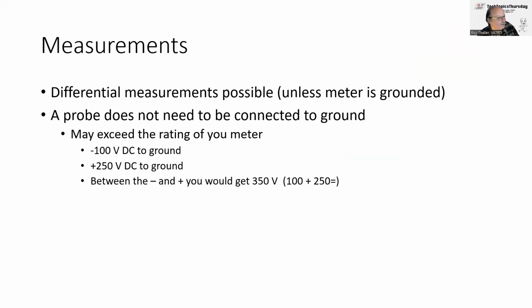For measurements, you can do differential measurements because the meter is not grounded, so you don't have to measure to ground like you do with an oscilloscope or a spectrum analyzer. We'll cover grounding next week.